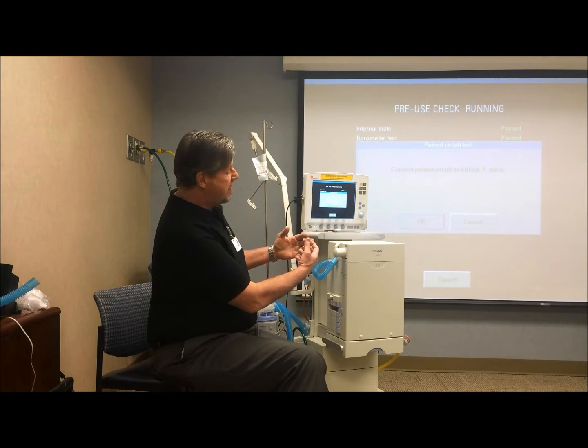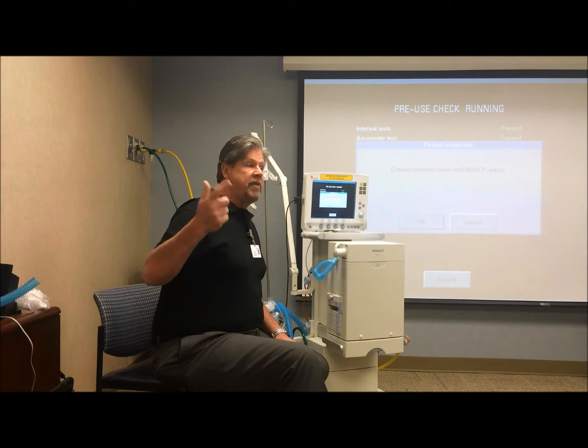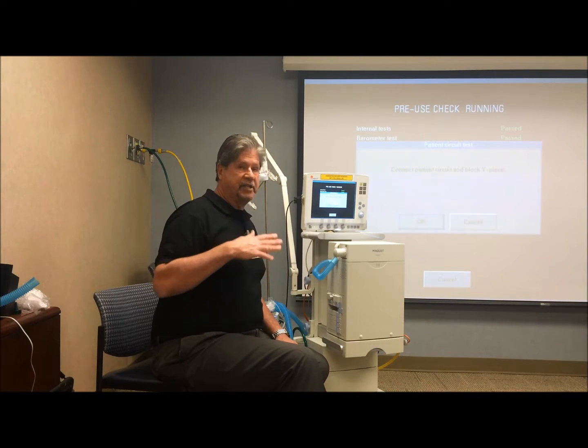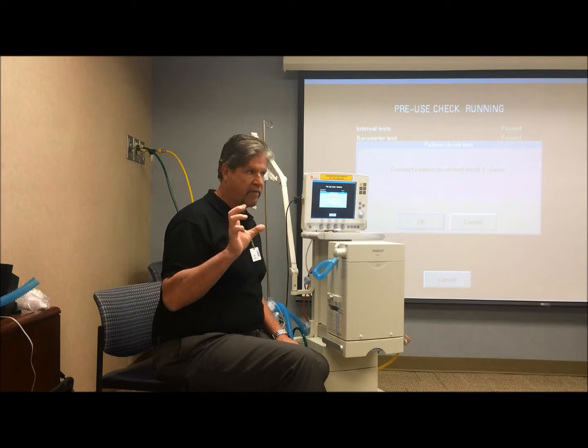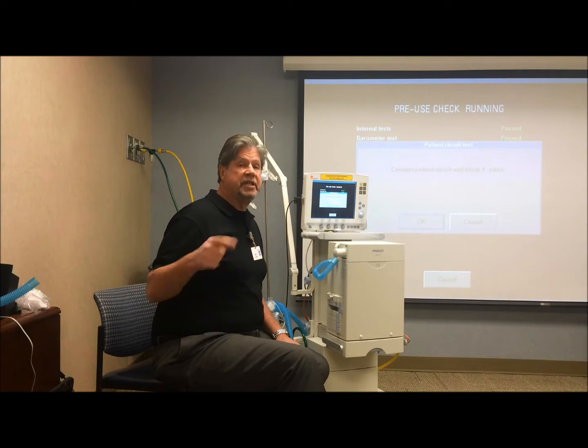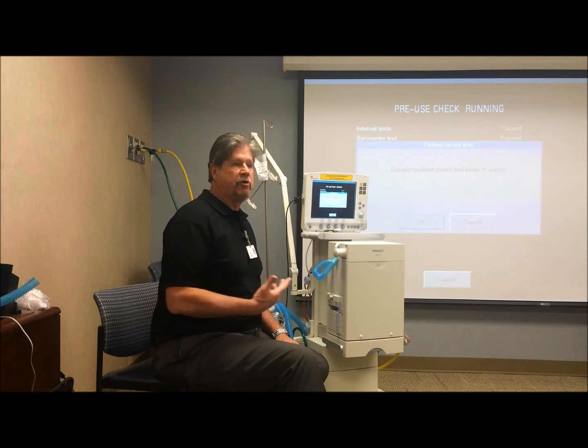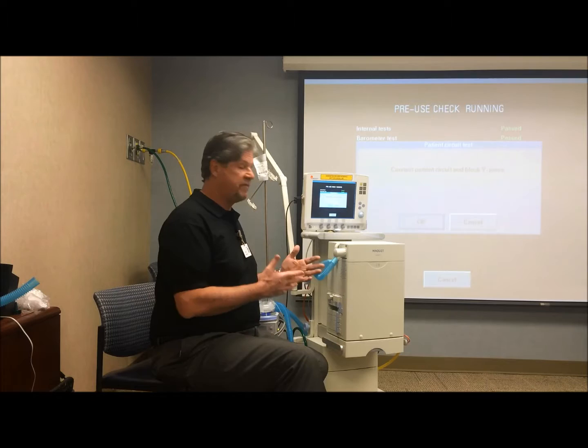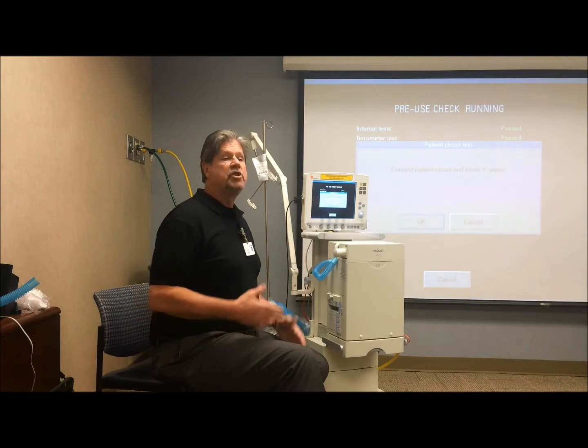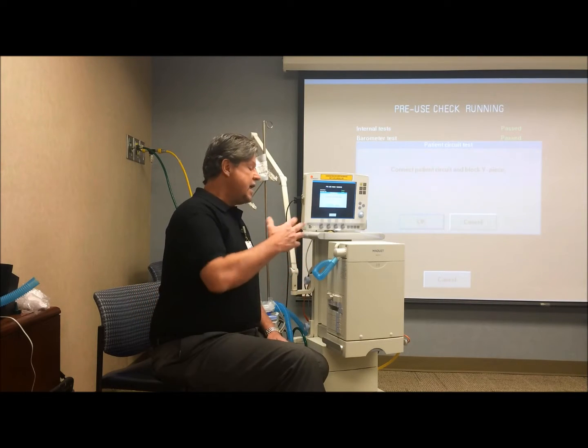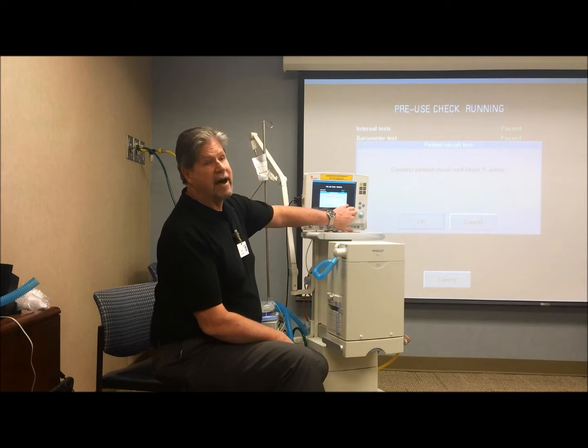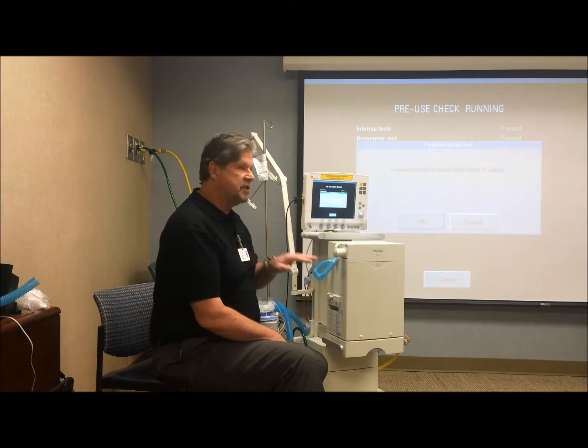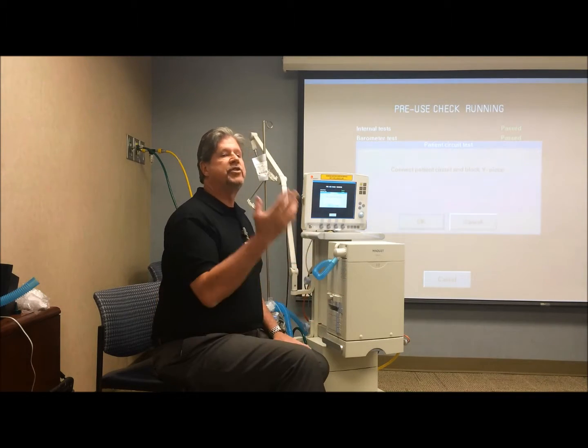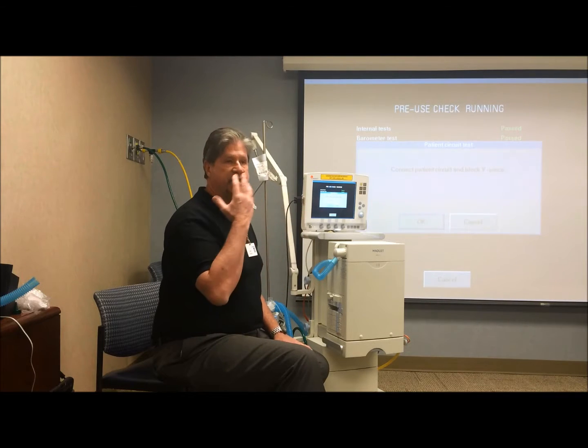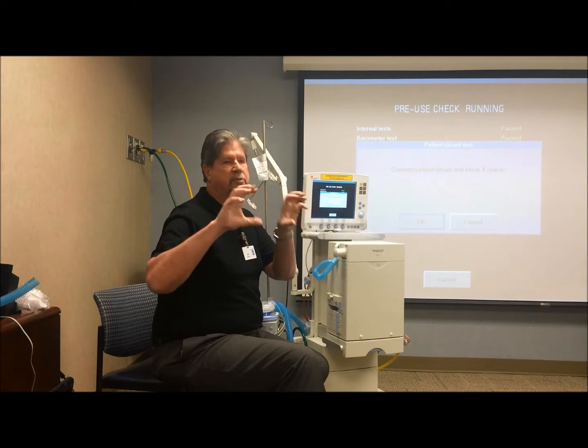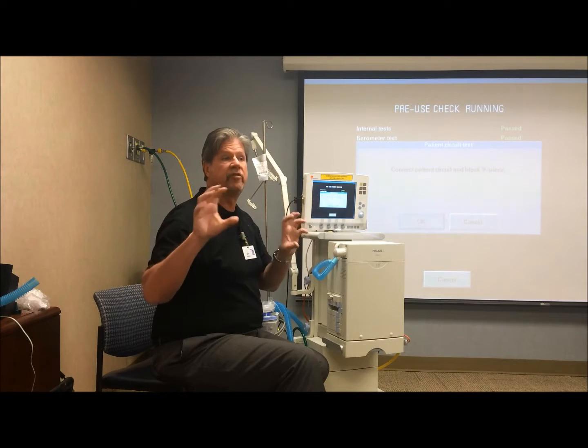So if the PIP is 30 minus the 5 of PEEP, your ventilating pressure is 25, and you're losing 2 cc's per centimeter of water pressure, you're losing 2 times 25, or 50 cc's to the circuit. So when you're ventilating your patient, even though the ventilator will say 500 cc's in and 500 cc's out, the patient is really only getting 450 cc's, because 50 cc's is being lost to the compression of the volume in the circuit.